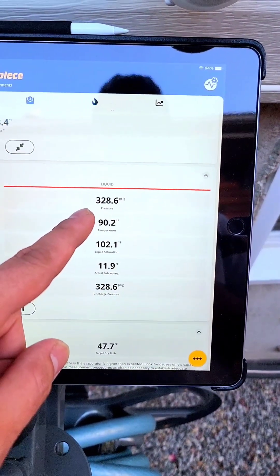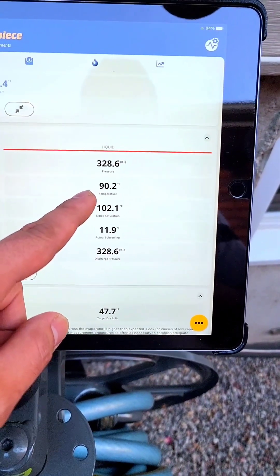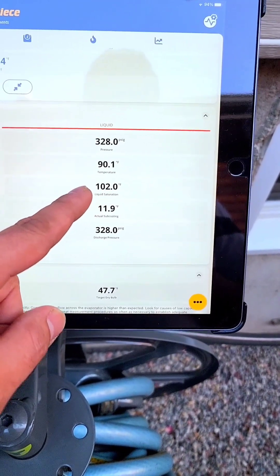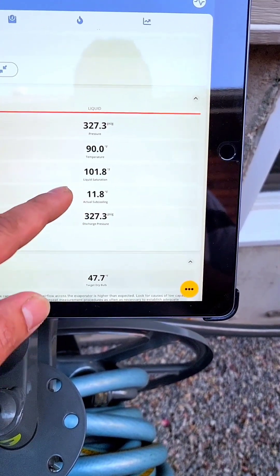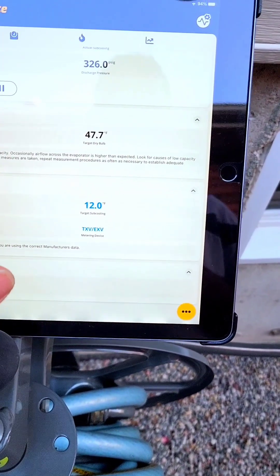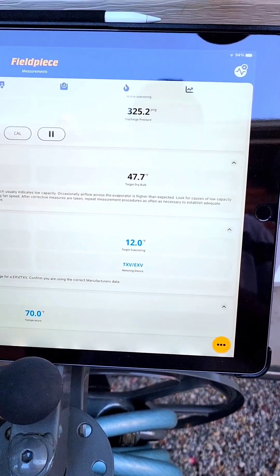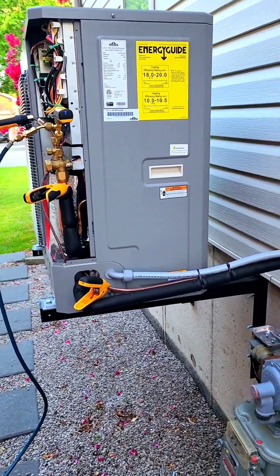My high side: I have 328 psi for the high pressure side, and then the liquid line temperature is 90.2. The liquid saturation of the condenser temperature is 102, and then the actual subcooling is 12 — it's fluctuating a little bit, but my target subcooling on this is 12. We always want to make sure the target subcooling on the Napoleon 2/3 ton heat pump, which is the one that we are looking at, is about 12 degrees.